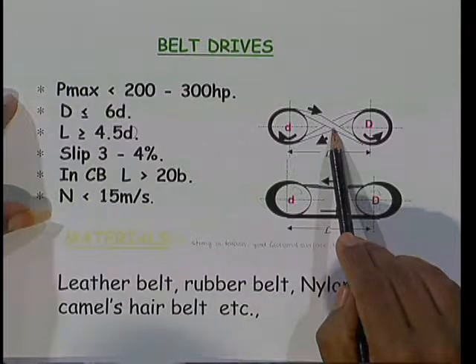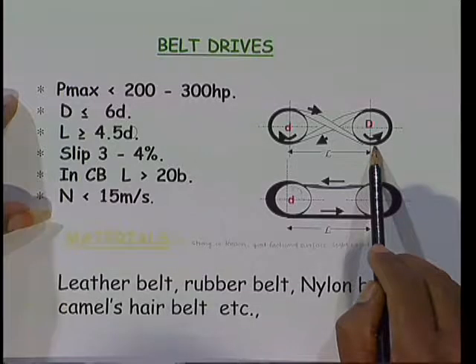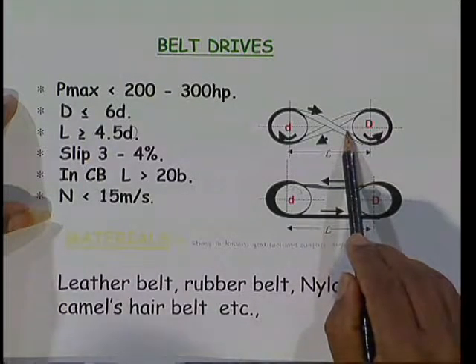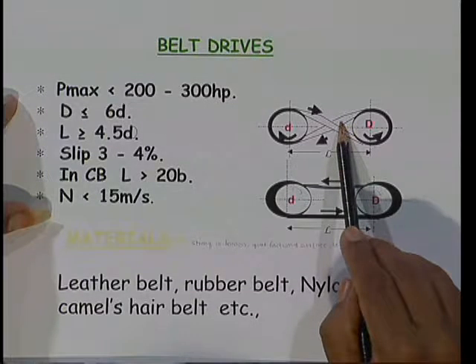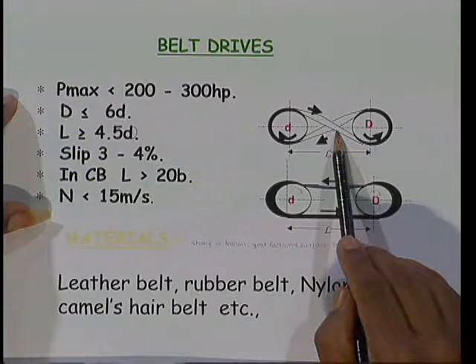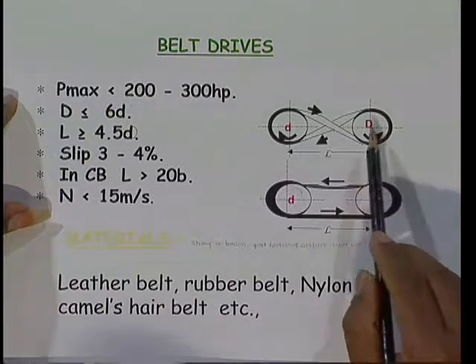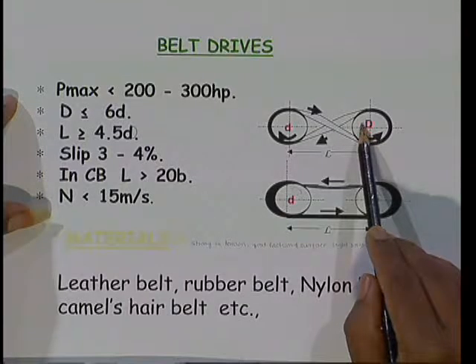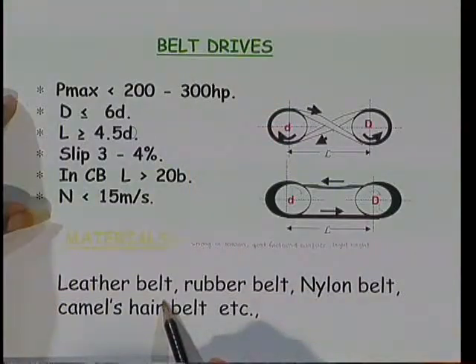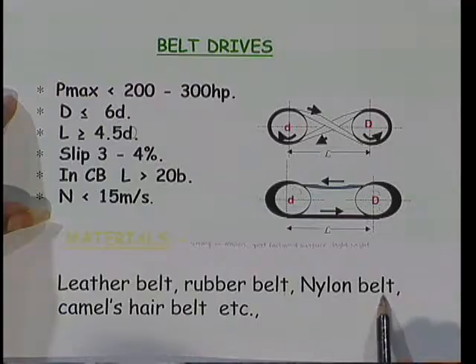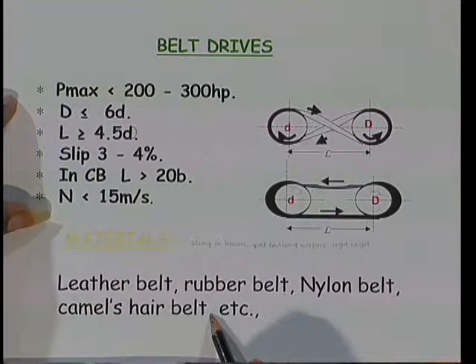If we require the motor pulley and load pulley to rotate in opposite directions, we connect the belt in a cross arrangement — called a cross belt arrangement. In this case, the length between the two pulleys should be greater than 20b, where b is the width of the belt. The speed should be less than 15 meters per second. Generally, this type of belt arrangement can transmit power from 200 to 300 hp. Belt materials are generally strong in tension, have good frictional surface, and are light in weight. Belt materials used include leather belt, rubber belt, nylon belt, and sometimes camel's hair belt.